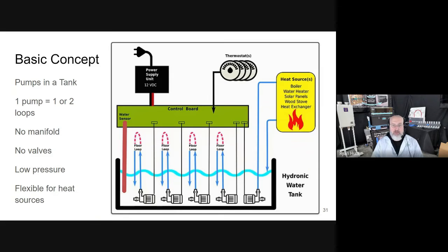But that whole system is controlled at low voltage. It runs on 12 volts, and there's a thermostat board. The board's function is to take 4 thermostats and tell each pump when to run based on a setting for it. But overall, it's extremely simple: no valves, no manifolds, low pressure, low voltage, and flexible heat sources.